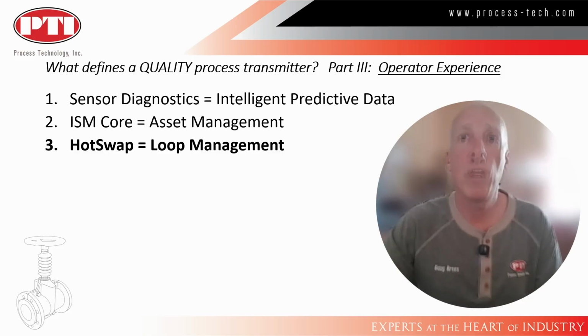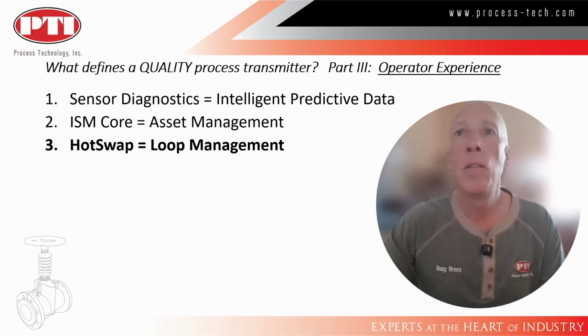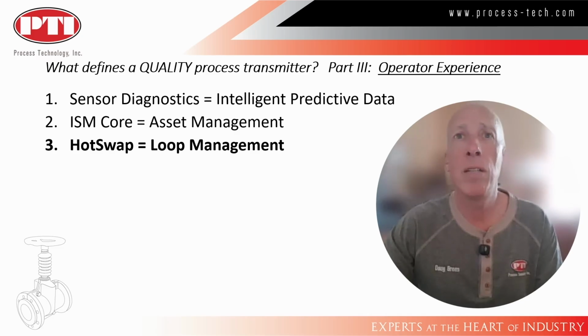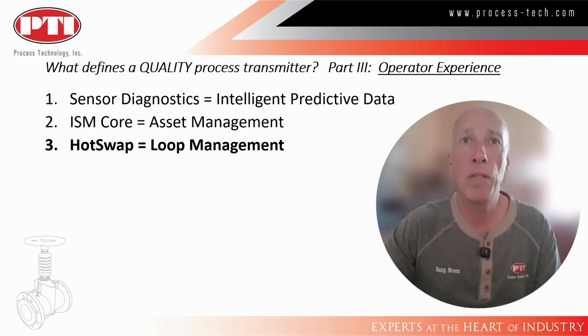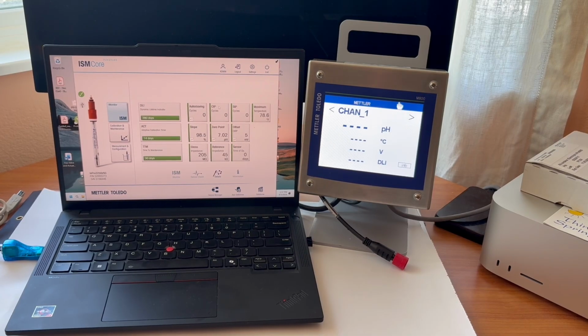Mettler was the first to introduce the hot swap concept. This was more than 20 years ago. It was a manual process that let you calibrate a sensor and write down the slope and the offset. You then had a menu option in the transmitter for data entry that let you manually type in the slope and the offset. With the development of digital ISM, anything manual is a thing of the past. Earlier, you saw the digital handshake of a sensor being connected to a transmitter. You saw how we performed a 2-point calibration using the ISM core software on a PC. The hot swap concept is calibrating sensors in an environmentally controlled instrumentation shop, I&E, whatever. And then simply go into the remote installation and in minutes swap out the pH sensor.